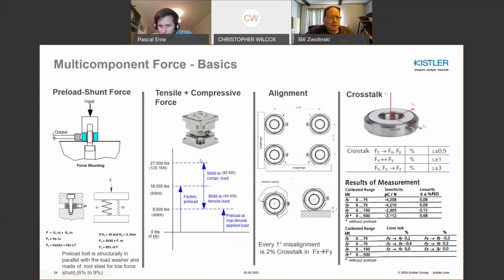Tensile and compressive force, usually you preload at 70% of the full scale range, and that gives you basically the ability of measuring both compressive and tensile forces with a margin. Alignment of sensors is critical. As you see, force sensors like this have a flat. They look circular, but they actually have flats on either side of the force sensor. These flats can be used to align the sensor, so you minimize any misalignment. For every 1 degree of misalignment in the sensor, you get a 2% crosstalk between X and Y.